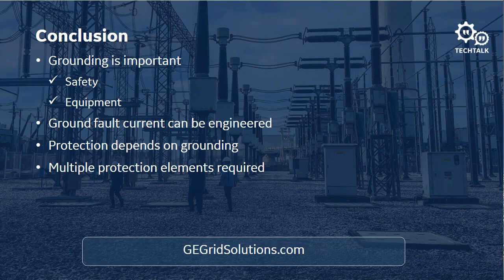So basically we need the voltage and the current that go into our 67N relay. That relay then looks at the angle difference between the current and the voltage, and based on that angle relationship it can tell if the fault is in the forward direction or the reverse direction. If the fault is in the forward direction based on that angle relationship, and the overcurrent element has also picked up, saying there is a fault current level high enough to pick it up, you need both of those to operate the 67N. I hope I did that explanation some justice, but it's better when we have pictures to explain how we look at those angular differences.